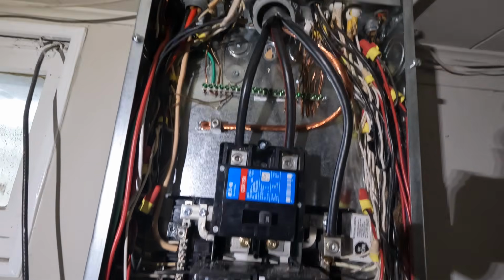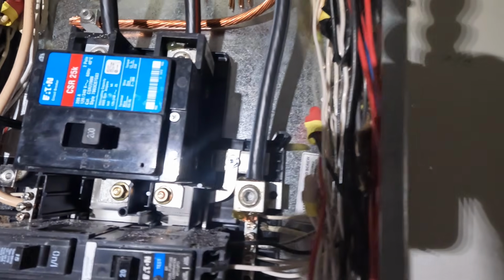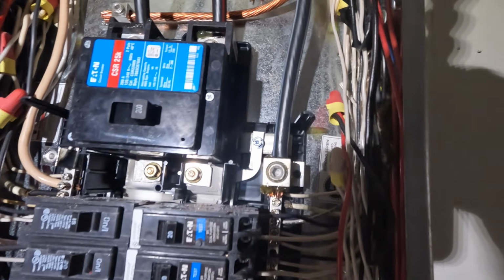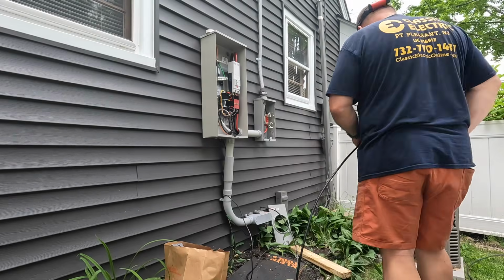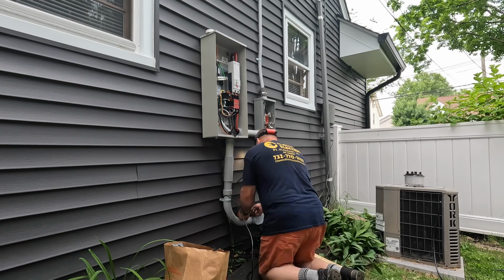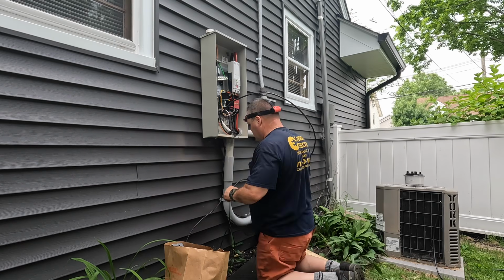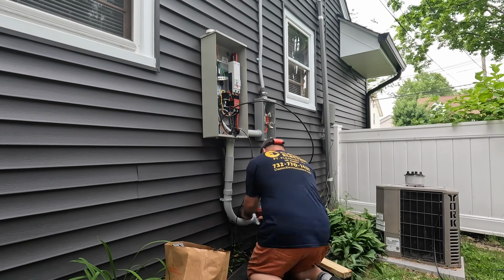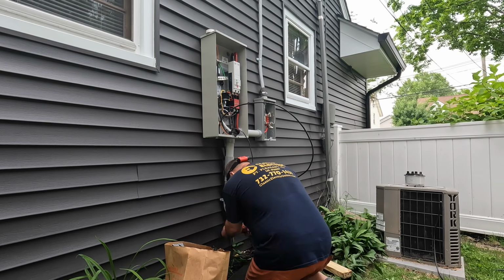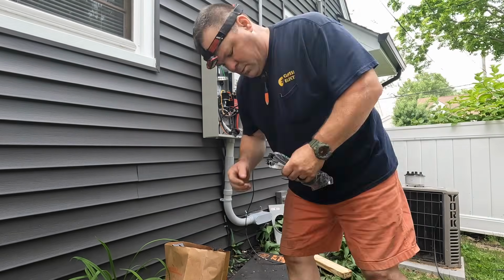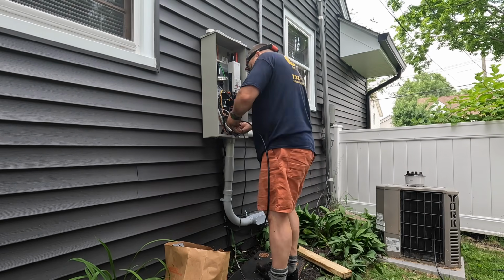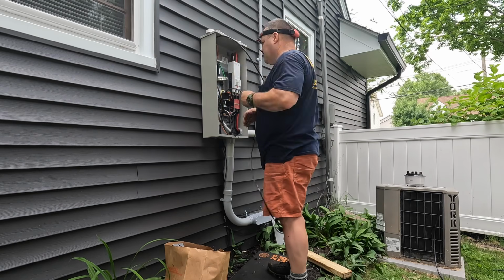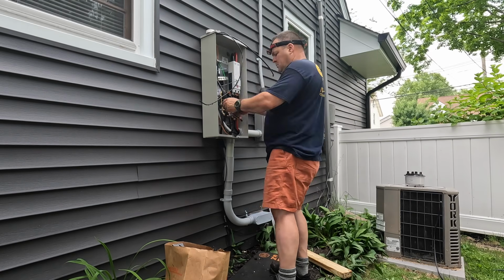So there you can see the lug that was bonded to the enclosure, and there's our grounded neutral conductor, our 2 new hots, and finally here on the outside, now that I've done the inside and we're done down in the basement, we come outside, we're going to connect all of our grounding electrode conductors. They're going to be attached to the ground bar, which is of course bonded to our grounded neutral inside this automatic transfer switch.